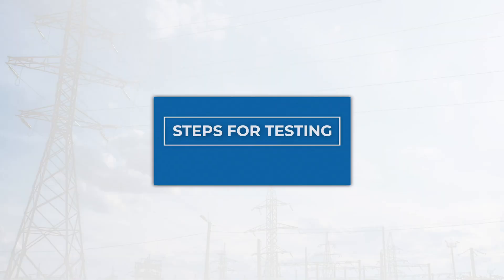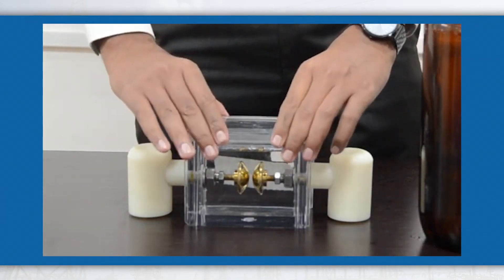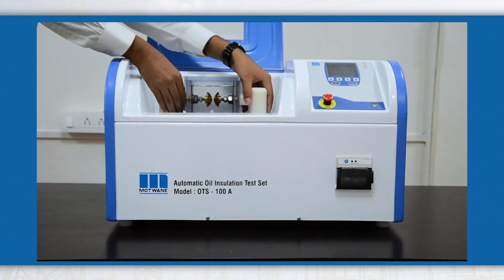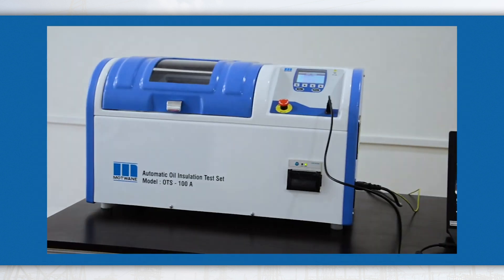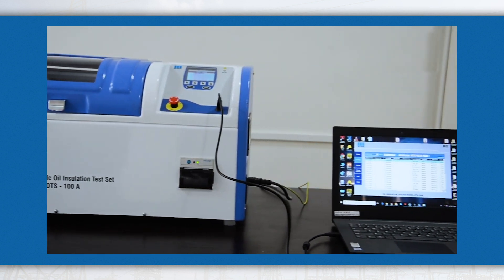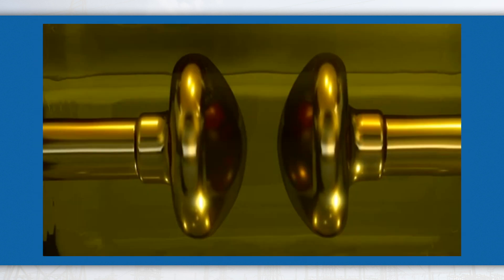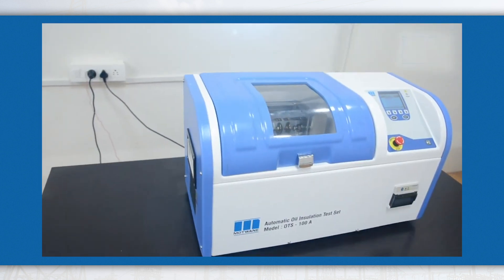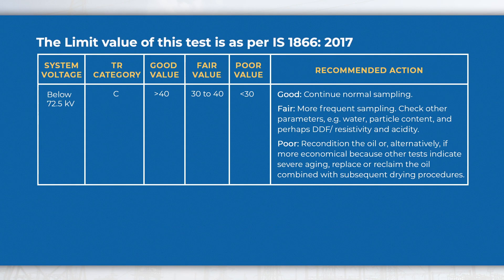This test is conducted by placing an oil sample between two electrodes and applying AC voltage gradually by not more than 2 kV per second, until the electrodes have enough potential and start to conduct through the oil. The limit value of this test is as per IS 1866:2017, given in the table.